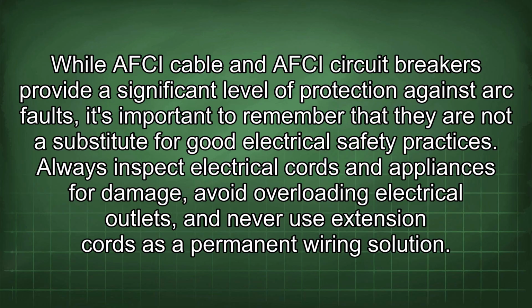While AFCI cable and AFCI circuit breakers provide a significant level of protection against arc faults, it's important to remember that they are not a substitute for good electrical safety practices. Always inspect electrical cords and appliances for damage, avoid overloading electrical outlets, and never use extension cords as a permanent wiring solution.